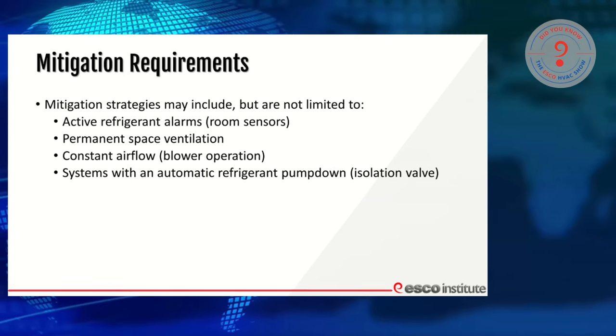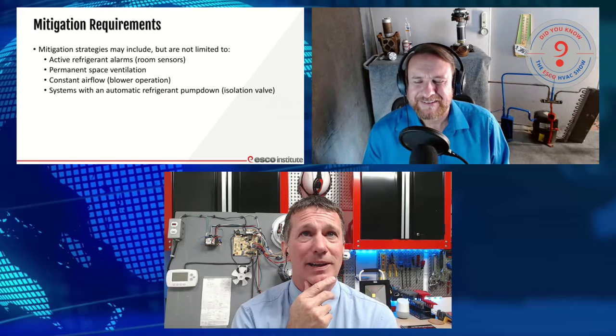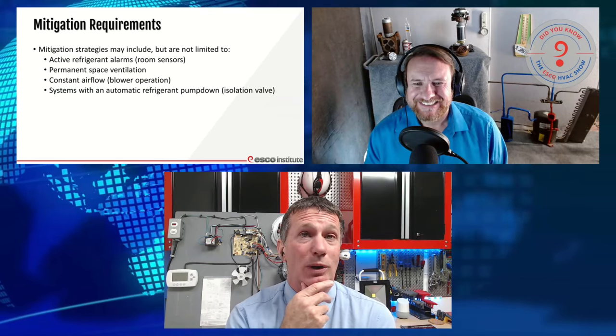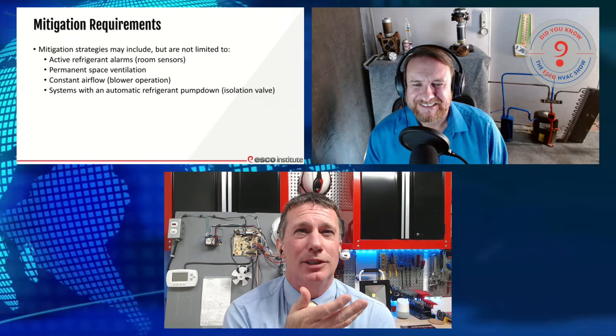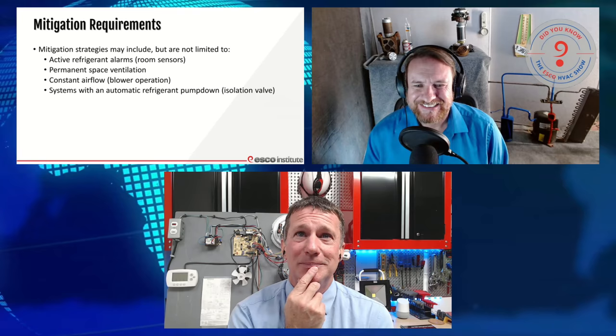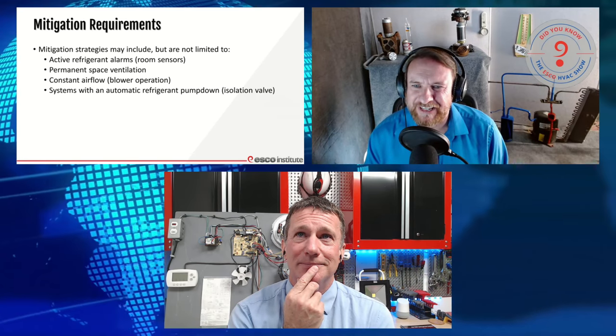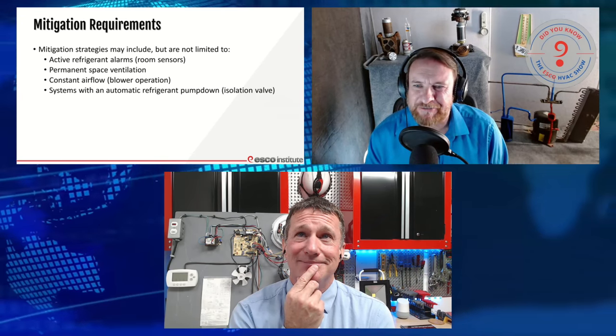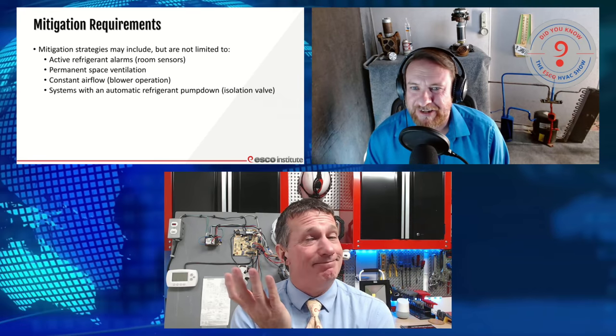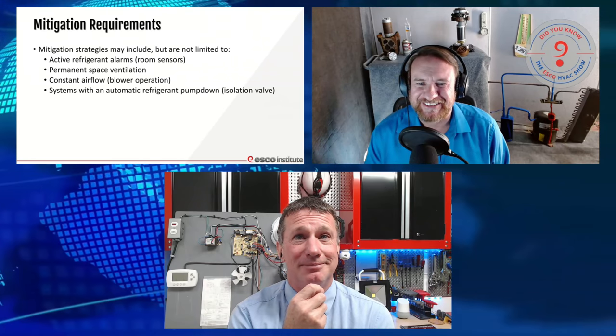If I had a system with an electronic expansion valve at the outdoor unit, what could I do to get as much of that refrigerant as possible out of the indoor space? You could just close that down, just like with a solenoid — it does an automatic pump down, just like in refrigeration. And now you don't have any refrigerant at the evaporator coil at all. And a side benefit: you don't have to worry about refrigerant migration to the compressor during the off cycle.